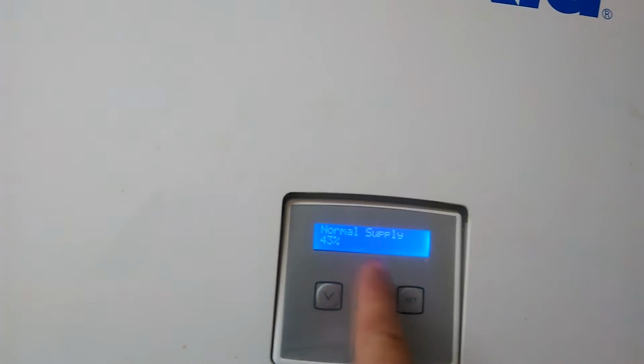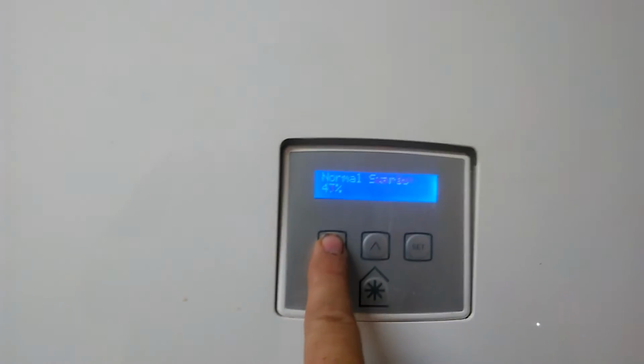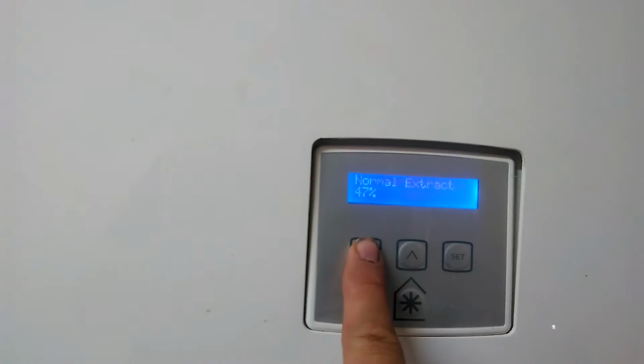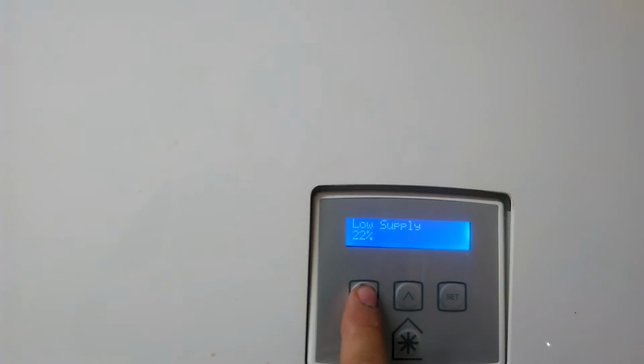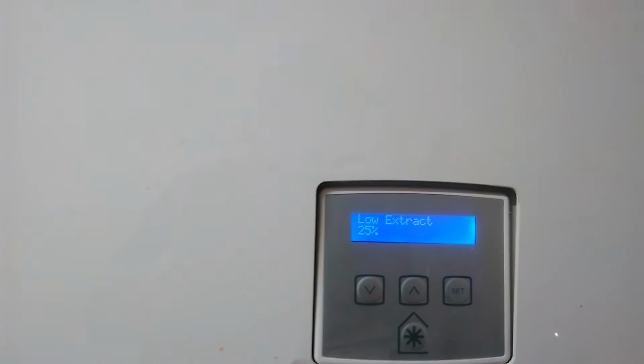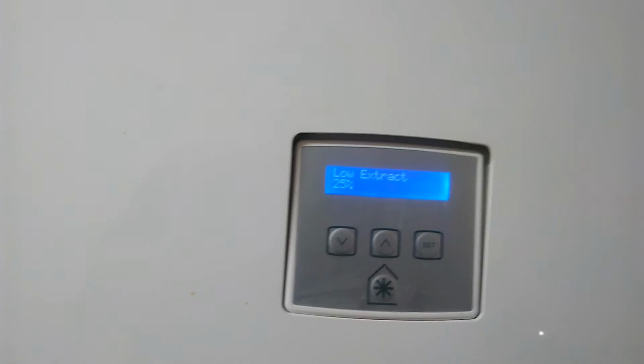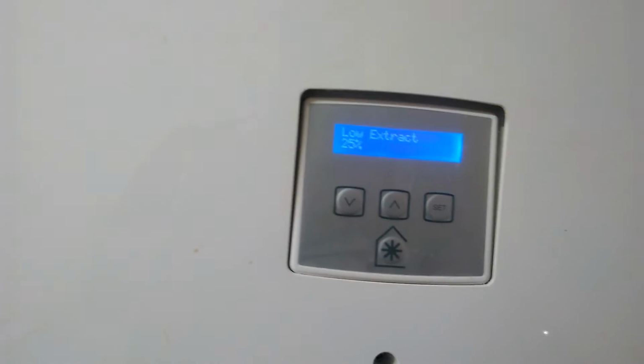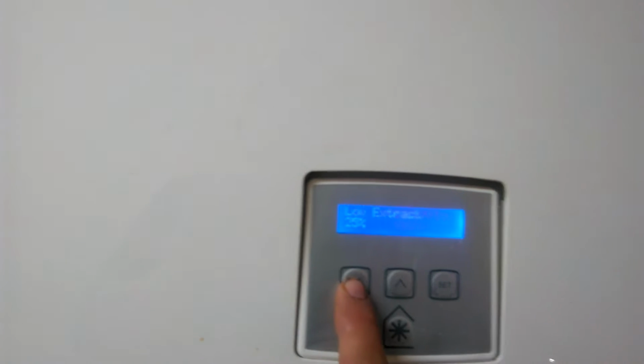So we'll move to normal supply, 43%. And the normal extract again is more because using the probe anemometer we've managed to balance the airflow. The low supply is 22%, and the low extract is 25%. This low mode is programmed in to operate during the evening hours, just if people are a bit conscious of noise. Plus, there's not going to be any showering or kitchen activity during the evening, so that's why we program in the lower mode. It helps with efficiency as well.